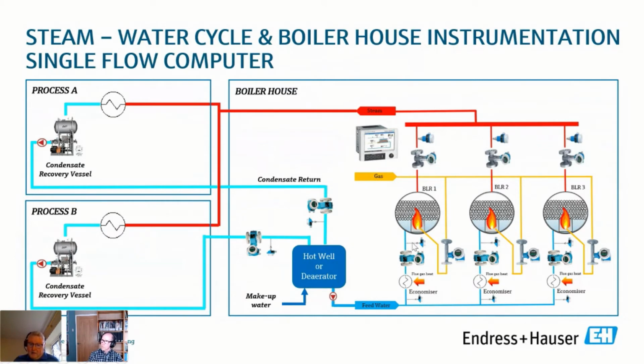By looking at the mass in and the mass out, we can look at the blowdown. By looking at the heat in and heat out and fuel in, we can look at the fuel steam efficiency. By looking at the condensate return, we can see how much of the steam we're getting back as water, so percent condensate return. So there's lots of KPIs we can do, and these can be performed in a box like this.